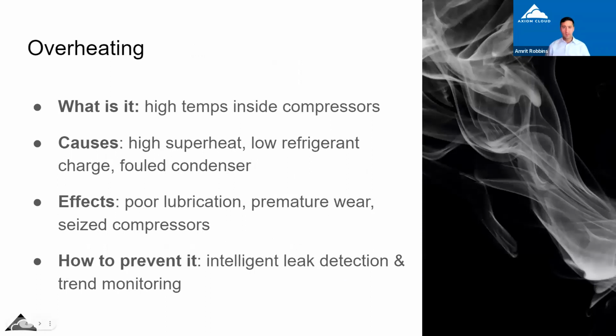All right. Next up, we have overheating. Obviously, overheating means the compressor is getting too warm, which is bad. That can be caused by high superheat, low refrigerant charge, or fouled condensers, among other failure modes. This can lead to poor lubrication, premature wear on the bearings, and seized compressors in the worst cases. That also leads to oil fouling and things like that, which can ruin everything else in the system along the way, all the other compressors too, and valves and whatnot.